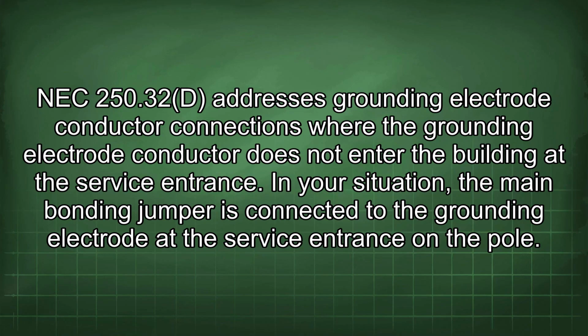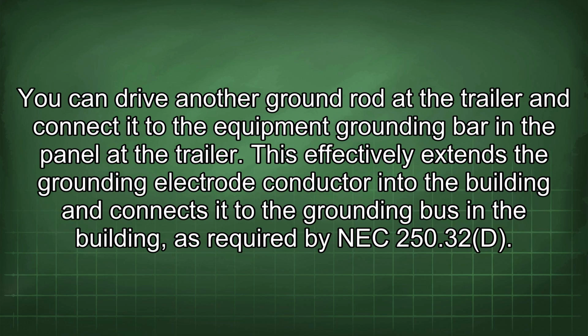NEC 250.32(D) addresses grounding electrode conductor connections where the grounding electrode conductor does not enter the building at the service entrance. In your situation, the main bonding jumper is connected to the grounding electrode at the service entrance on the pole. You can drive another ground rod at the trailer and connect it to the equipment grounding bar in the panel at the trailer.